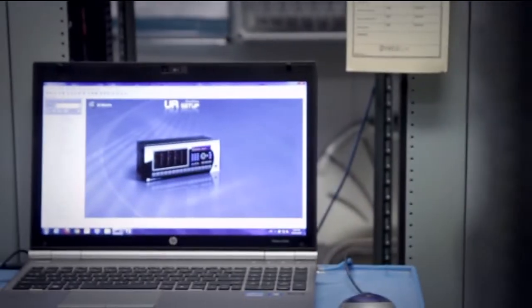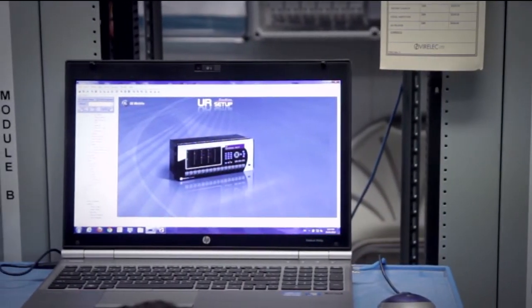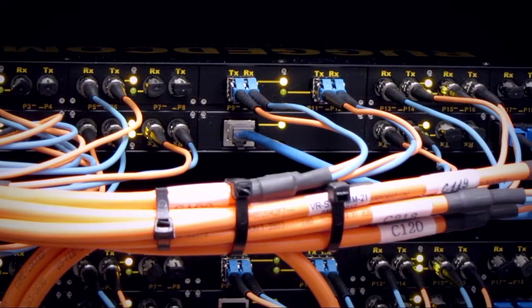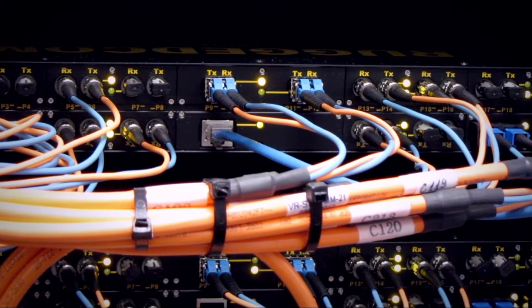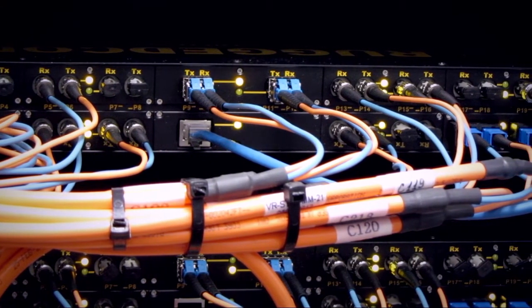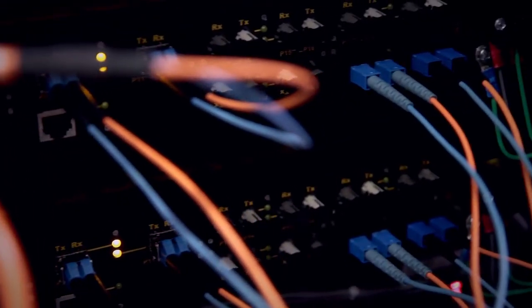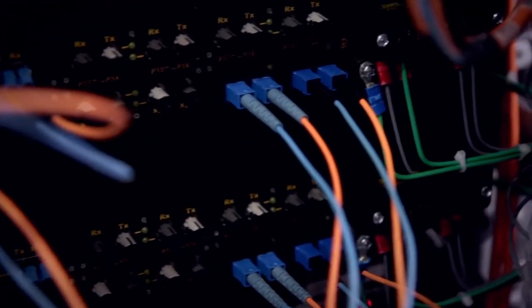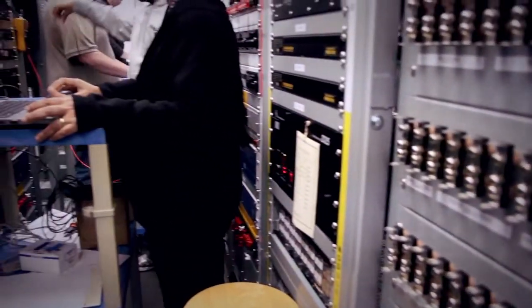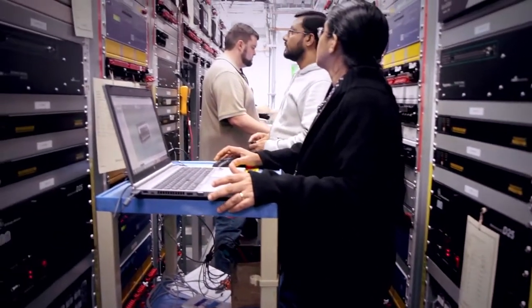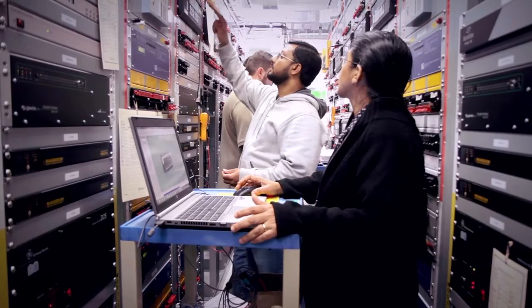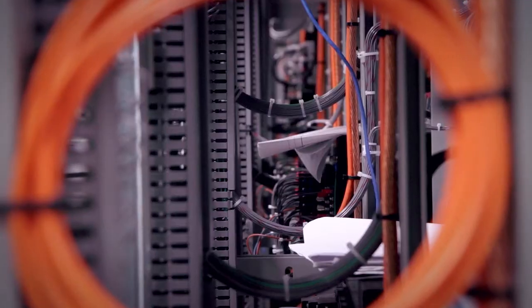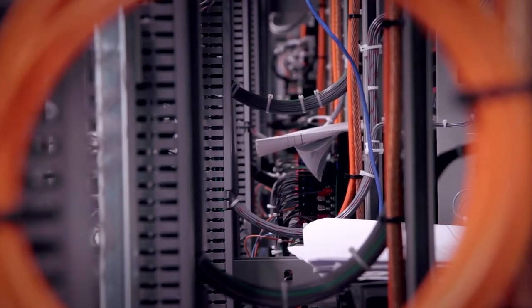More advanced system testing, or FAT, factory acceptance testing, as it has become commonly called nowadays, can also involve setting up the communications and networks amongst the various devices in the panels. Typically, testing involves SCADA system point lists containing analog and digital data points.